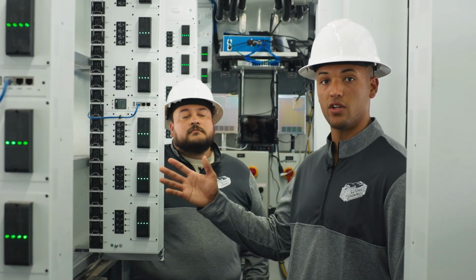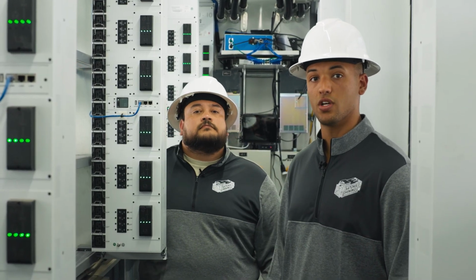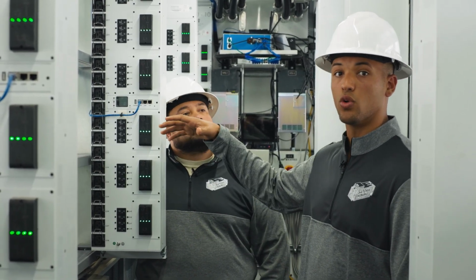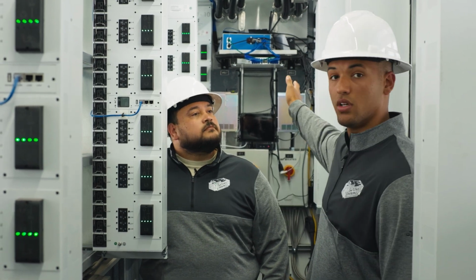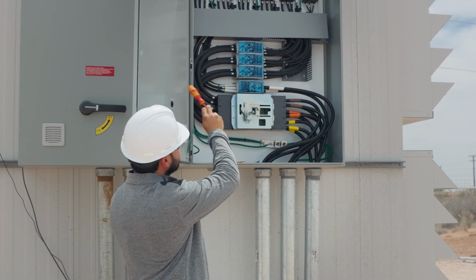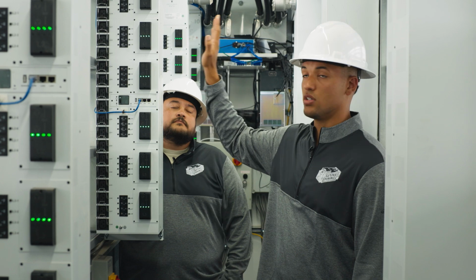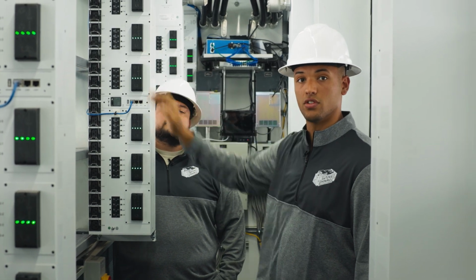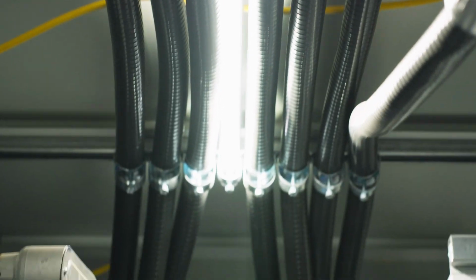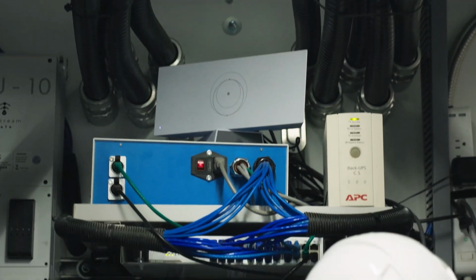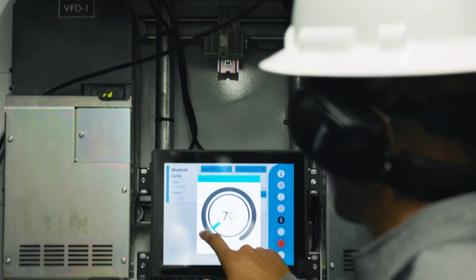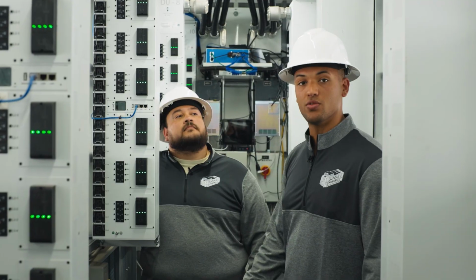So as we saw outside with the 2550 kVA transformers that we have, our power is stepped down to a lower voltage. It's ran through the electrical panel that you can see on the outside of the containers, and then it's distributed to each of the 10 PDUs that you see here in front of us. As you can see here above us with these big black electrical cables that are running overhead, it delivers a lot of electricity to each of the PDUs we see here in front of us.